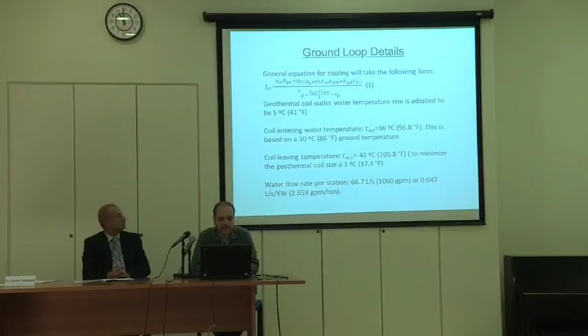For the sake of this study, we considered that the ground temperature is 30 degrees. Why we took it higher than 26 was just to take into consideration any unforeseen conditions that may arise within the project. Since in our design the ground temperature is 30, the water leaving from the ground temperature, we took it as 36. Why 36? To leave at least 6 degrees difference between the ground temperature and the leaving water from the ground to have an efficient heat exchange.